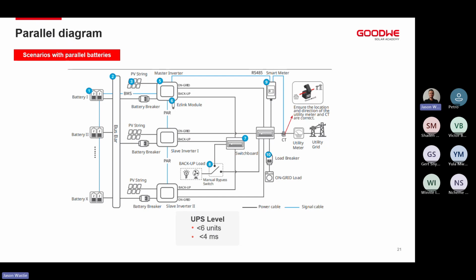Parallel connections. So we've got two different ways we can parallel the system using the GoodWe inverters. One is using a common battery bank, parallel batteries, and then the other we'll look at shortly. So when we parallel the system, the only additional hardware from GoodWe that we would need is the physical EasyLink module. An EasyLink module is a communication module that we use for the GoodWe inverters. And that EasyLink module we would connect into the master inverter, and the slave inverters we connect via a parallel cable or signal communication CAN cable.